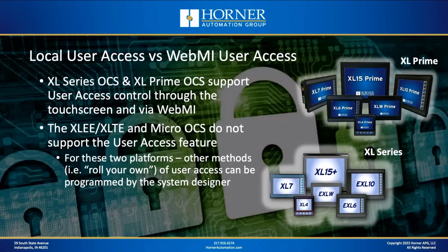Now, only certain models support the user access feature in the touchscreen itself, and that is limited to the X5, the XL series from the XL4 on up, the entire XL Prime series, and in the future, the entire Canvas series will also support this feature. Now, if you happen to be using an XLE or an XLT, or maybe even a micro OCS series product, it doesn't mean that you can't protect certain screens or certain objects. You can, it's just you'll need to kind of roll your own functionality in that regard. And it's definitely possible in the near future we could do a video on that topic showing you an approach you might take to solve that particular situation with one of those two products.